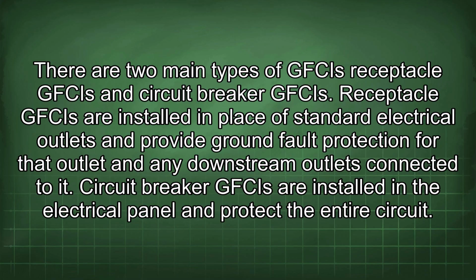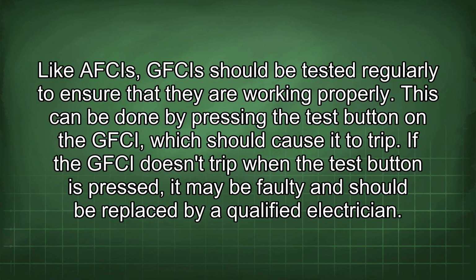Receptacle GFCIs are installed in place of standard electrical outlets and provide ground fault protection for that outlet and any downstream outlets connected to it. Circuit breaker GFCIs are installed in the electrical panel and protect the entire circuit. Like AFCIs, GFCIs should be tested regularly to ensure that they are working properly. This can be done by pressing the test button on the GFCI, which should cause it to trip.